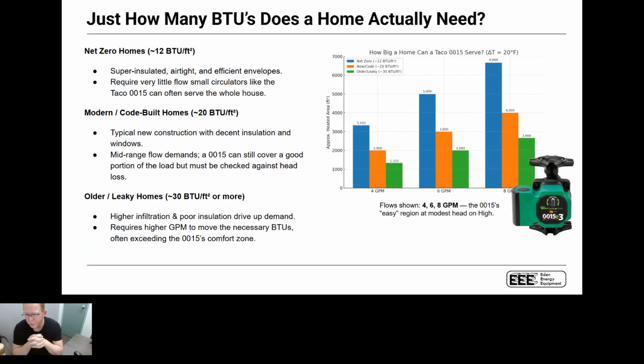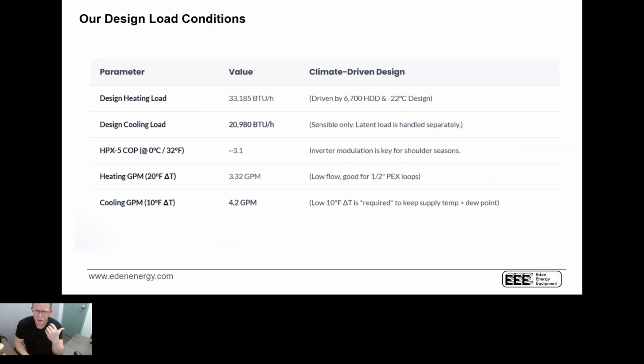It can be upwards of the entire 6 tons can be delivered into the space just using a single circulator. So the beauty of an air to water system is we got to understand that loads are getting smaller and we can achieve a lot with a very simple baseline system. As we look at some of the design load conditions, we talked about this earlier, but we're looking at a design heating load of roughly 33,000 BTUs, a design cooling load of roughly 21,000 BTUs, and that would peg my HPX5 at about a COP of 3.1, depending on what I'm doing from an emitter standpoint.